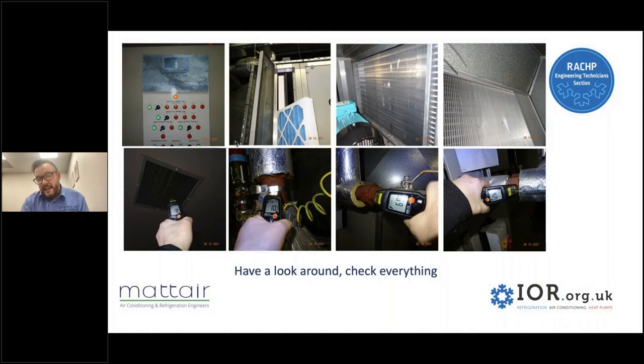Then in the next picture, you can see the heating coil was at 42 degrees C, because that was activated by the BMS in its normal mode. So we had all three coils activated, but we had no faults on the panel, and we had a pretty reasonable air off, and everything looked clean. My point is that from a maintenance point of view, we've got to be looking at absolutely everything, because the BMS guy goes, there's no problems there. The aircon or refrigeration engineer, who may be the one responsible for cleaning filters, finds no problems anywhere. As a quick look around this air handler, everything looks fine, but it totally isn't.